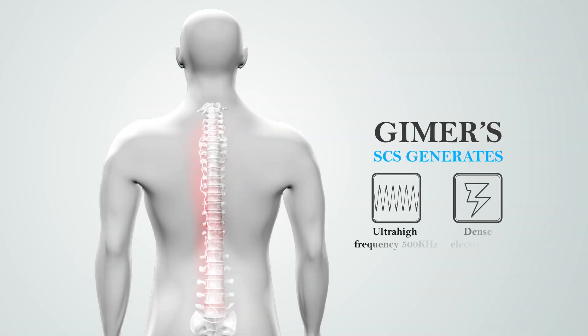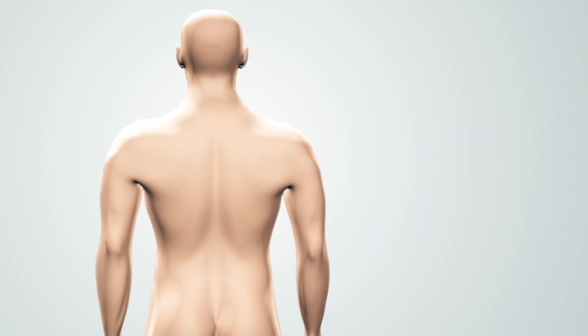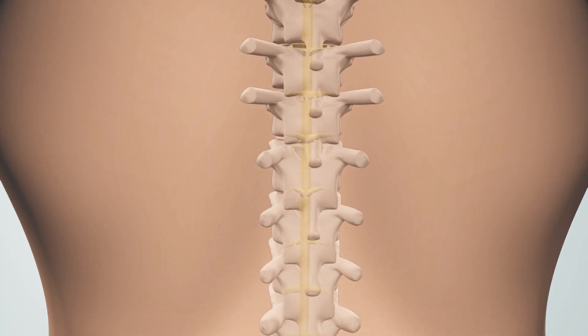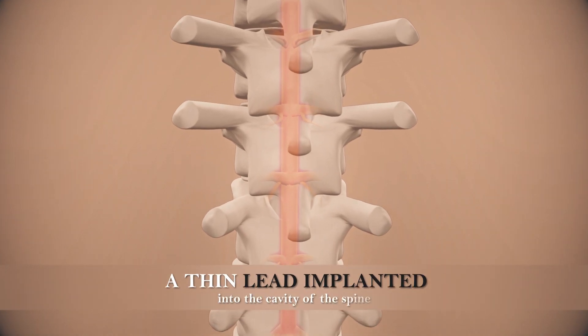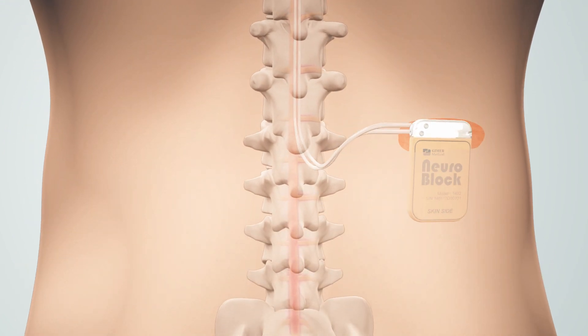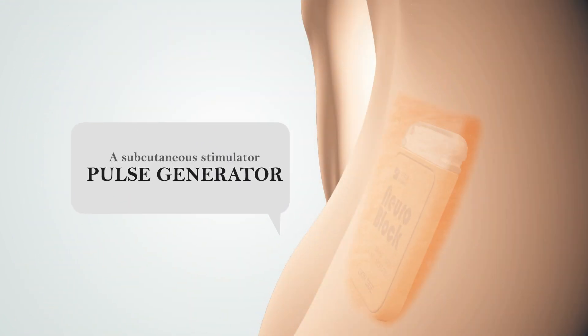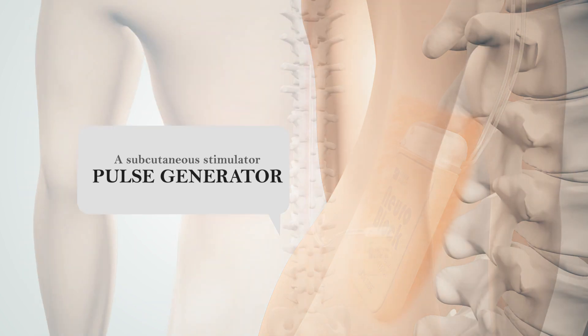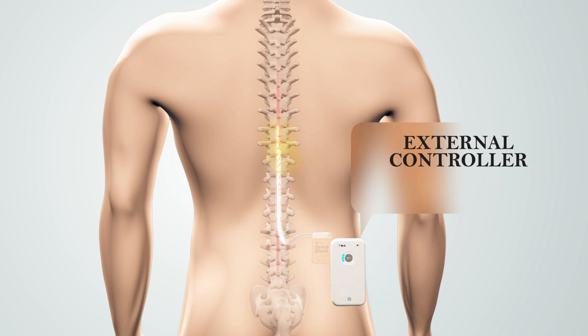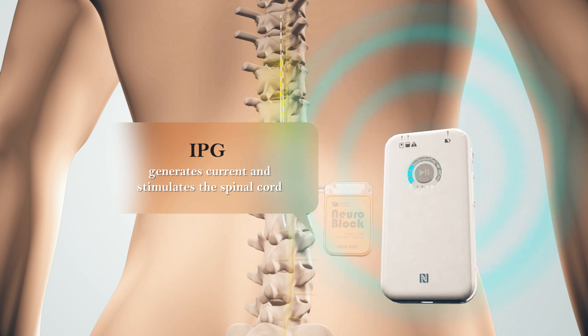Gimer's SCS generates ultra-high frequency 500 kilohertz dense electric field to stimulate the spinal nerves and suppress the transmission of pain signals, thus effectively reducing pain. It comprises three parts: one, a thin lead implanted into the cavity of the spine; two, a subcutaneous stimulator pulse generator; three, an external controller. When the patient feels pain, they can use the controller to start the stimulator, which in turn generates current and stimulates the spinal cord.